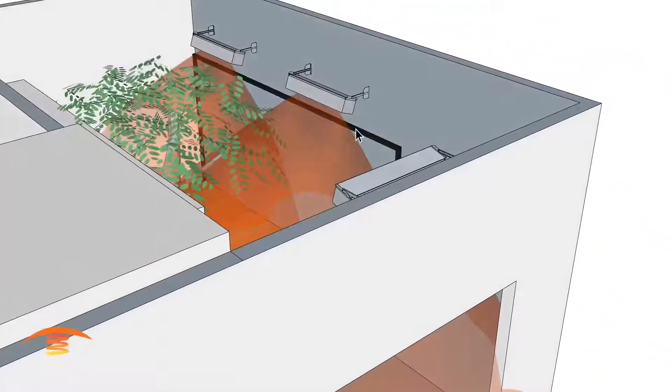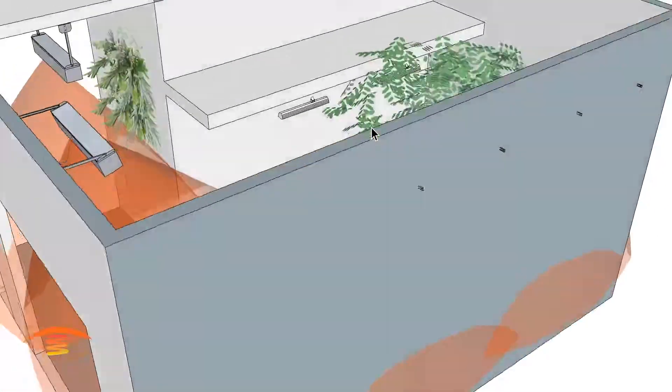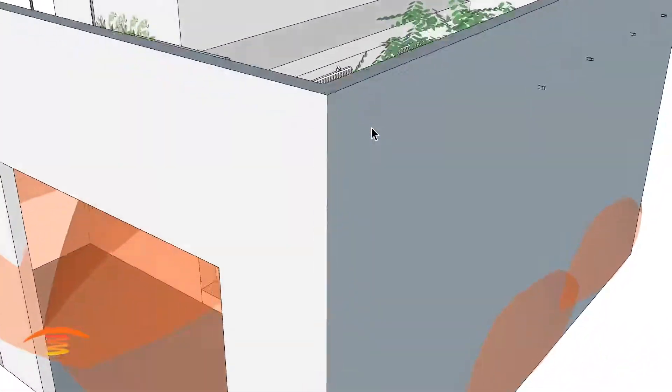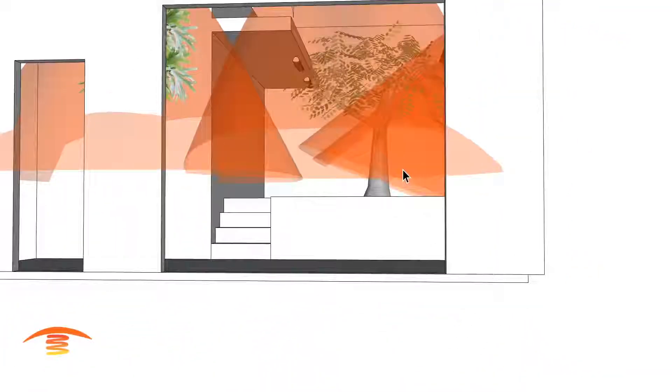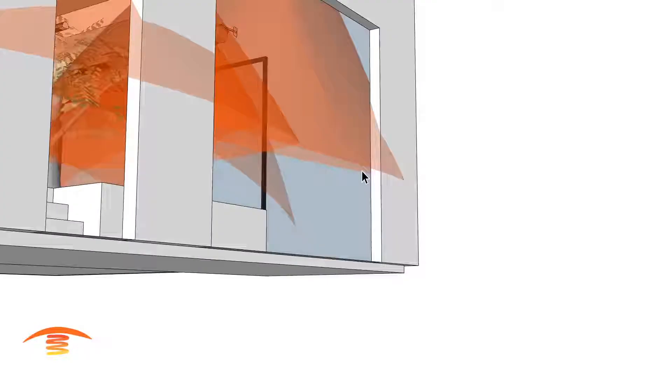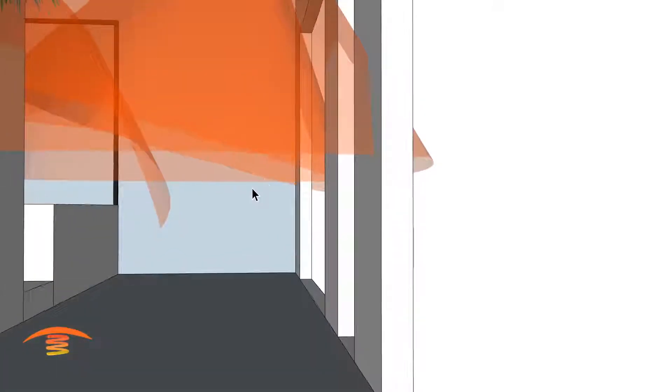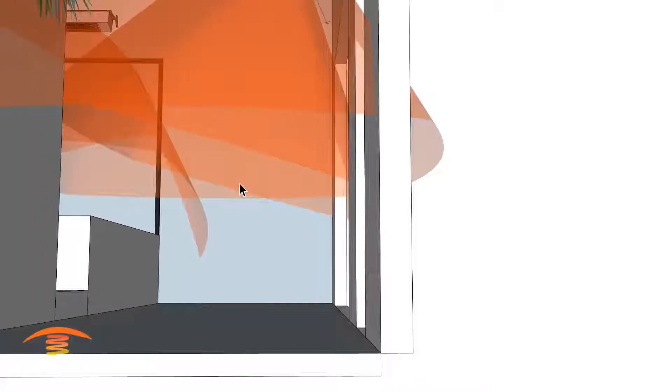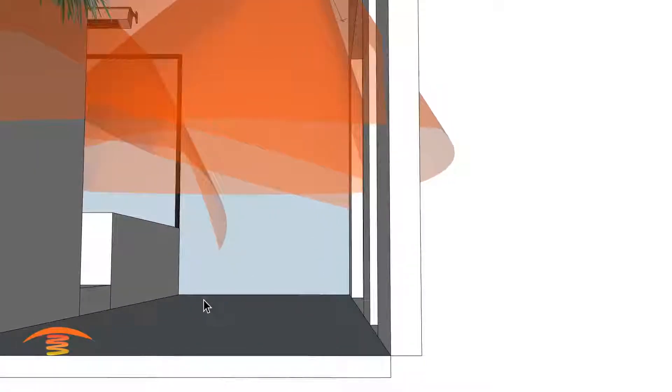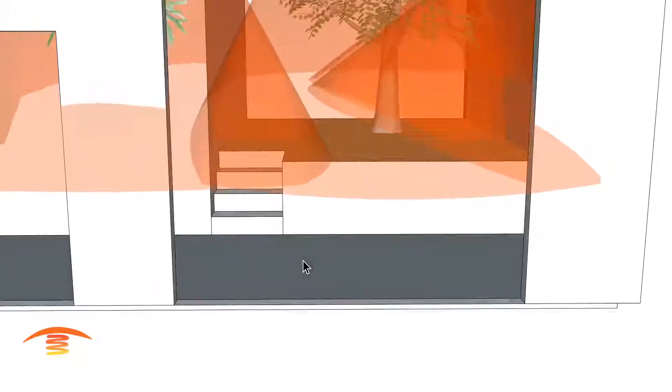So, yeah, you can see the coverage here. We have the predicted coverage is ideal for eight feet off the ground. And you can see we have these much higher, but this ray continues to travel and will warm up this space and make it much more comfortable than what it is existing today.